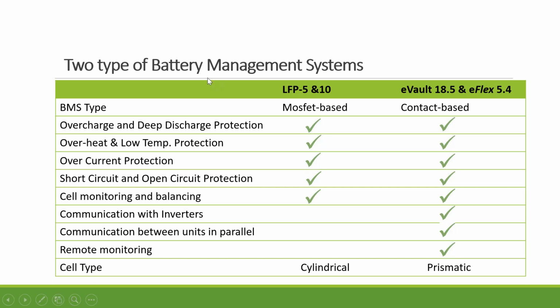On the market for lithium batteries, in general there are 2 different battery management systems: one's called MOSFET based, another's contact based or relay based, using a solid state relay for example. The difference is that the contact based BMSs can handle larger charging and discharging rates. If you need big systems, the contact based is much better. It provides longevity and is more robust.